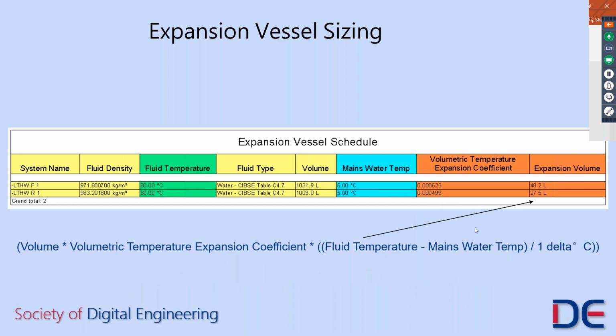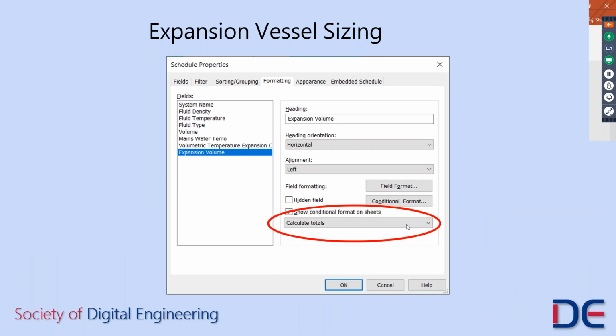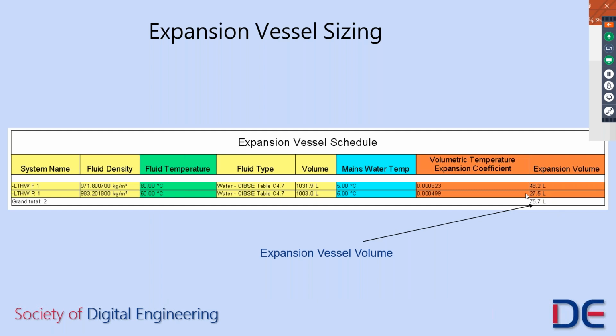We can then use that coefficient to multiply that by the volume and the delta T, and that gives us our expansion volume for that part of the system. So the flow at 80 degrees has this volumetric expansion coefficient, gives that expansion volume. The return system at a lower temperature gives this volume. We can then look at the parameters within that table, and for our expansion volume, we can say, let's calculate the totals. Then if we go back to our schedule, we can see it's summated those parts, and 75.7 litres is the expansion vessel volume for that system as it exists.